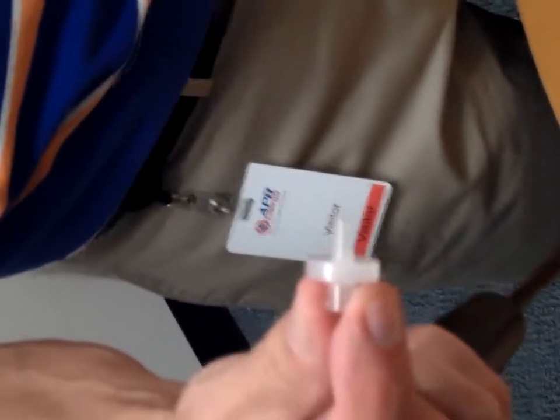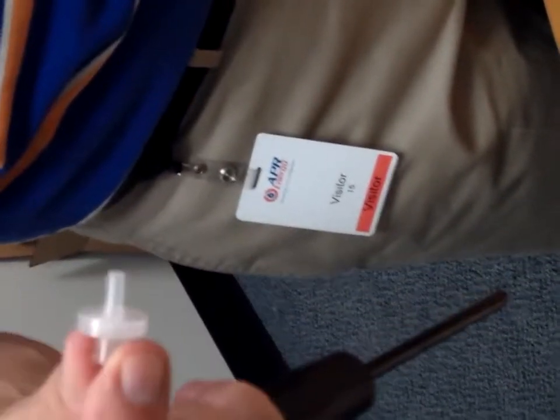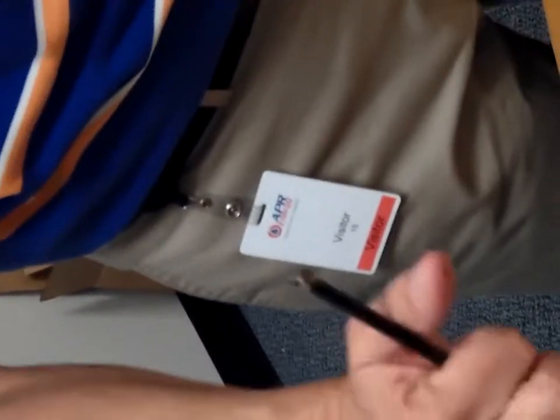You doing good so far? Yeah, definitely. All right. Inside the probe on here, there's a water stop filter that you get to like so. You can just simply pull that apart, and then you've got what we call a hydrophobic filter. What this does is stops dirt. It also stops water. So if you were to drag the tip into any kind of water or fluid, it would all stop here.